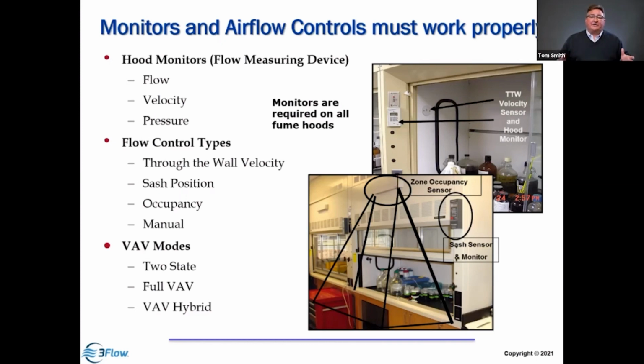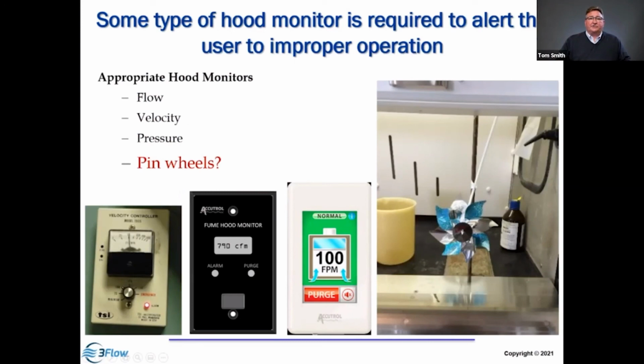So installing VAV controls is a great idea from controlling to a demand-based operation and saving energy when the hoods aren't in use. But if you go too low or they don't control properly, then we can create safety issues that can come back and eliminate any of the value of the energy savings. If the hood's not functioning properly and somebody gets exposed or there's an explosion, the energy savings are irrelevant at that point. We need to be safe first. So monitors are really important. They can measure face velocity, they can measure flow, they can report pressurization.